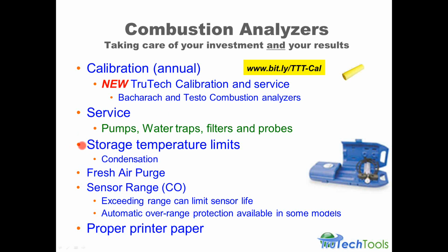You do want to pay attention to storage temperature limits, especially because condensation inside the analyzer, if you go too low a temperature, can actually freeze and crack things. So you want to make sure you take good care of the equipment and you bring it in during the coldest weather.